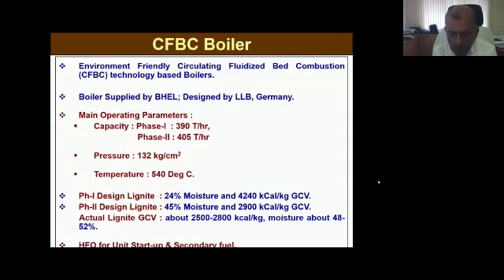This moisture went to 45%, then when we commissioned the new plants in 2010, we saw there was degradation in the fuel, so we changed the GCV and moisture content as well - from 24% to 45% moisture, and the GCV went down from 4,240 to 2,900. So there have been significant design changes, particularly considering the fuel, in the combustor size, rotary equipment design, ESP, and other things.